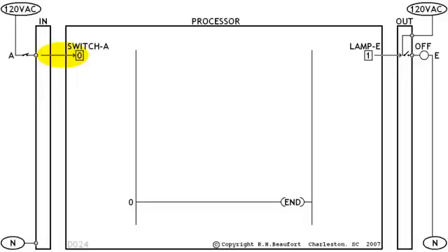This little arrow shows the direction of the transfer, but now we need to talk about when the transfer actually takes place. We'll use this symbol to show step number one of a three-step scan cycle sequence. In normal operation, the processor does this step in the scan cycle several hundred times each second, and each time it does, it updates the status of the input bits with fresh information from the input module. Remember that we're still looking at all of this in slow motion mode.